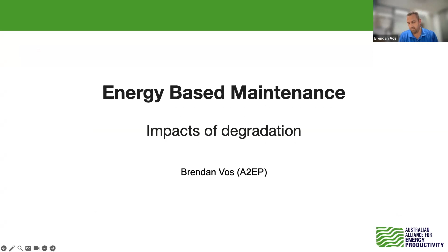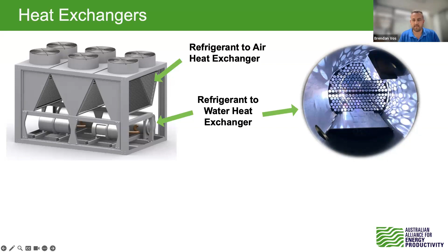this ground previously. So I come from a chiller background, main chilled water plant, and a lot of the fouling happens on the condenser side of the system or a coil side of the system. So I focused a little bit there. Just some really basics for anyone that's not aware. On top there is a refrigerant to air heat exchanger, and on the bottom is refrigerant to water at a really basic level. I put a really nice picture here of something we were building when I was in my last company, of just how that bottom heat exchanger looks, to put some premise around all those little holes where copper tubes go through and get filled up with water. So that's going to premise my next slide.